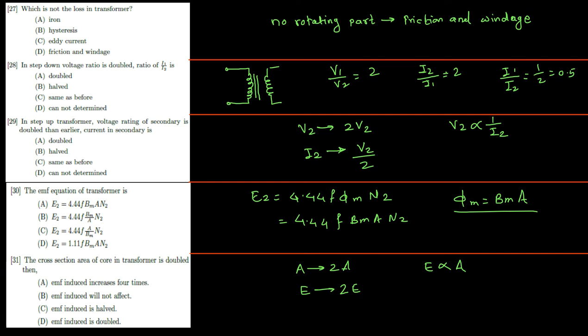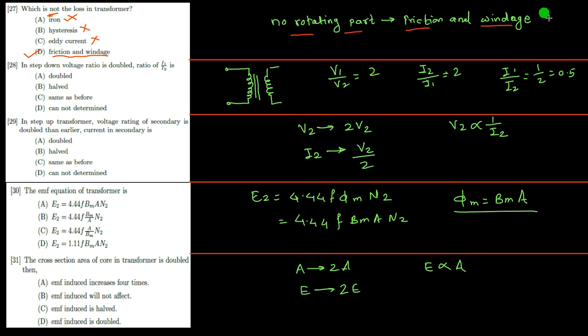Which of the following is NOT a loss in the transformer? Iron losses include eddy current and hysteresis losses — these occur in the transformer. Eddy current losses are also present. However, friction and windage losses are NOT in the transformer, because there is no rotating part. Hence friction and windage losses do not exist in a transformer.